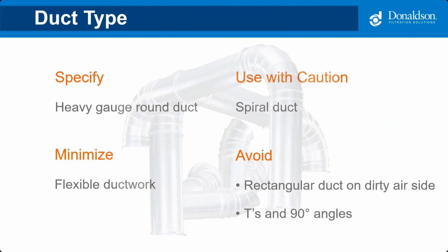Okay, just a few quick pieces of advice when it comes to duct type. Rectangular duct is commonly used in HVAC applications where you are moving air only, but we don't want to use it in industrial applications because dust settles out in the corners. It's okay for the clean air side though. When specifying industrial duct systems, make sure to call out round heavy-duty industrial ductwork. Most dust collection applications will use class 2, 3, and 4 ductwork, which are designed to SMACNA standards.